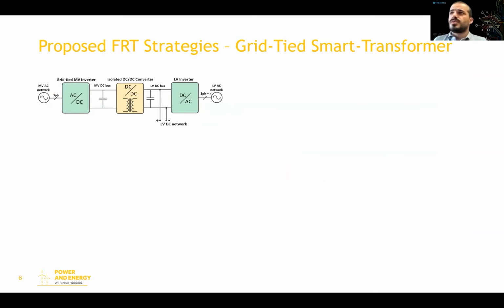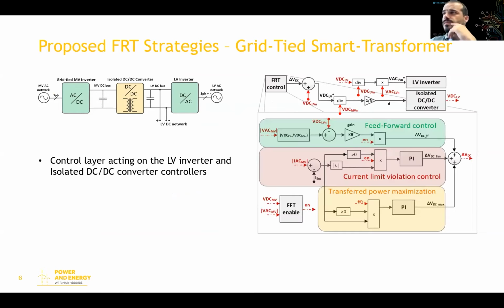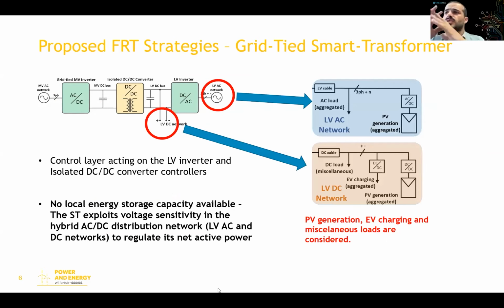Talking now about the proposed fault ride-through strategies, I will start with the one developed for the grid-tied smart transformer. It is basically a control layer which acts on the low voltage inverter and on the isolated DC-DC converter controllers. Since no local energy storage capacity is available, this strategy exploits the voltage sensitivity in the hybrid AC-DC distribution network to regulate its net active power. It does so by regulating the voltage in the low voltage DC bus, and also the magnitude generated for the low voltage AC grid.